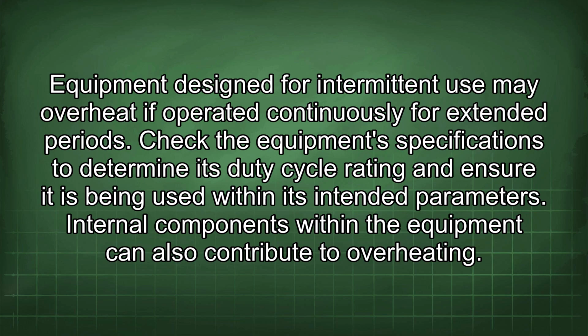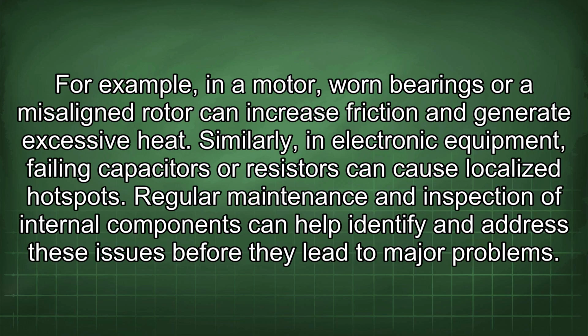Internal components within the equipment can also contribute to overheating. For example, in a motor, worn bearings or a misaligned rotor can increase friction and generate excessive heat. Similarly, in electronic equipment, failing capacitors or resistors can cause localized hotspots. Regular maintenance and inspection of internal components can help identify and address these issues before they lead to major problems.